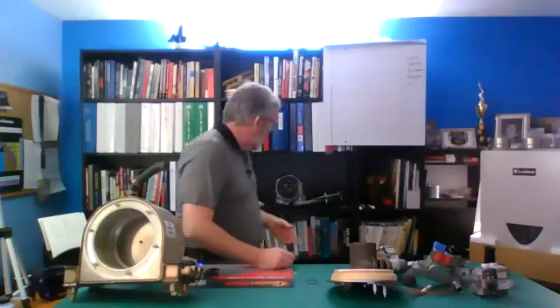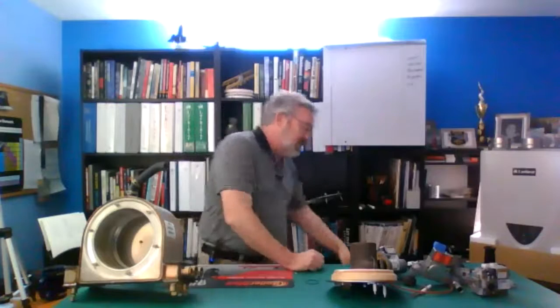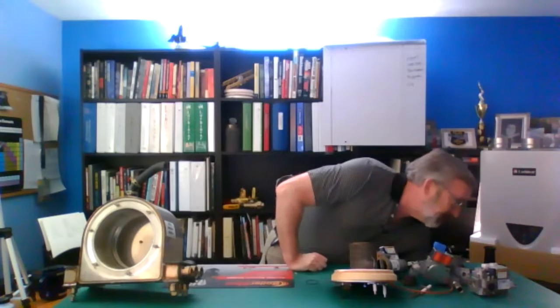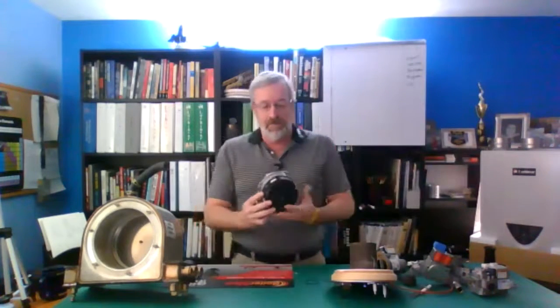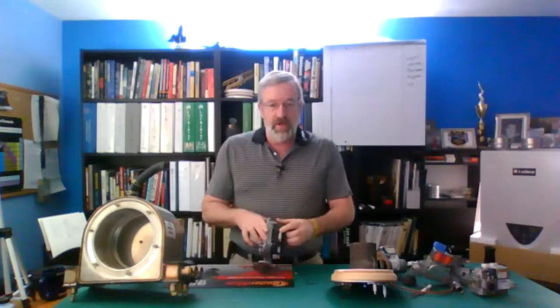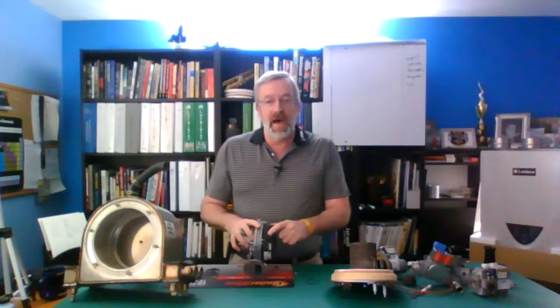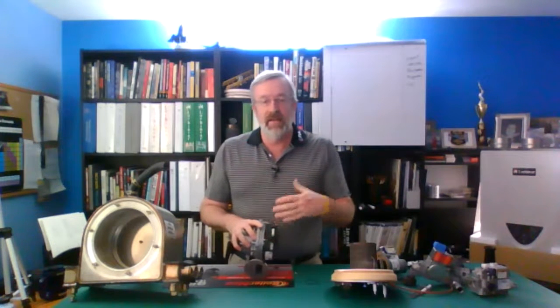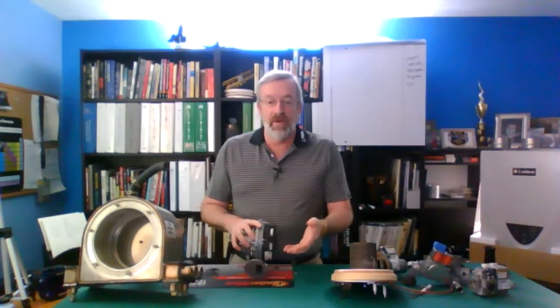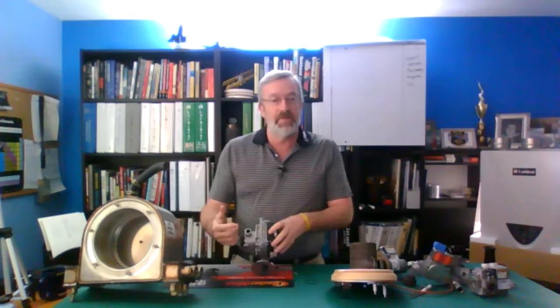my fan has 2 connections on it. This guy was hiding on me down there. I got 2 connections. I got a 3-wire and a 4-wire. The 3-wire is power. So as long as this is connected and my boiler is powered up, when I disconnect this 4-wire, my fan is going to run to 100%. It's going to run to its maximum speed.